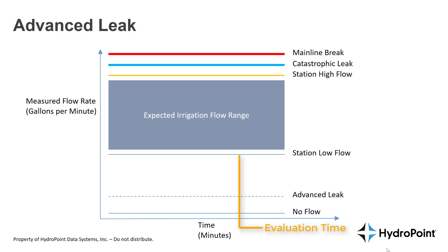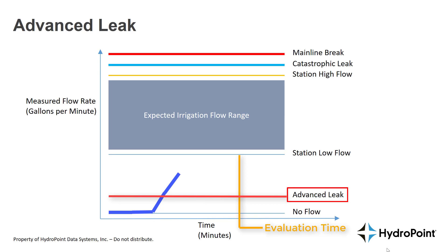To say that a different way, what an advanced leak alert is telling us is: with your OptiFlow controller, when no irrigation was scheduled and no manual irrigation was running, enough water began to run through the system to pass the advanced leak threshold. And then that leak condition lasted long enough to pass the evaluation time, which prompted the advanced leak alert and closed a normally open master valve.